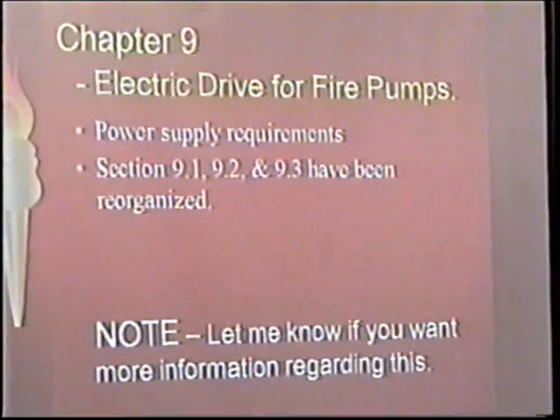And ultimately, the only control we have, or I have as a controller salesperson, is that I'm supposed to make sure that the controller is installed per 20. And if it's not, my only lever is the warranty or the liability coverage on the controller. Because technically, if it's not installed properly, it's probably outside of its listing. So those are the issues, and now it covers things like connections. When a contractor comes into the fire pump controller, you're supposed to use a watertight fitting. I've been able to tell them that in the field, never been able to enforce it. It's in 20, which means that hopefully now it's going to find its way into 695 in the National Electric Code next rewrite.